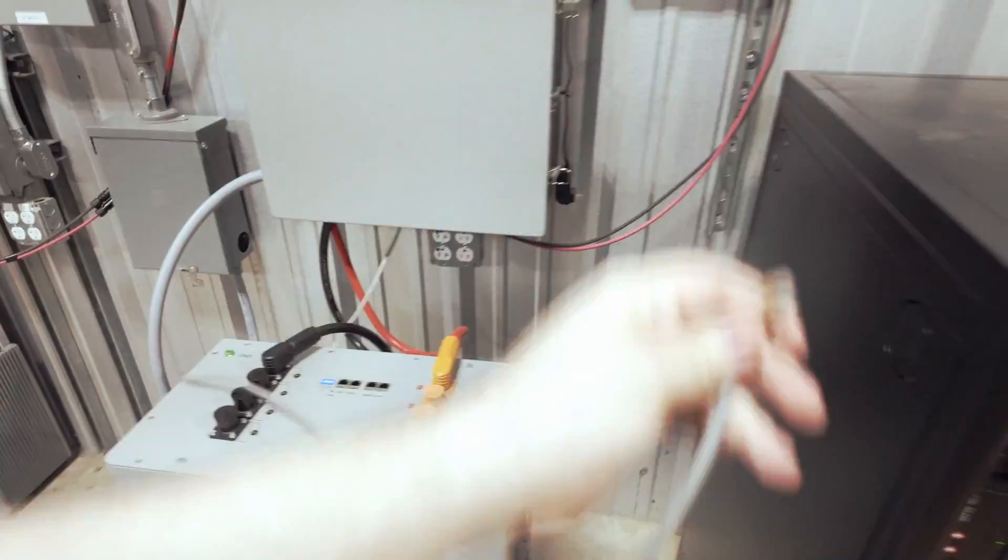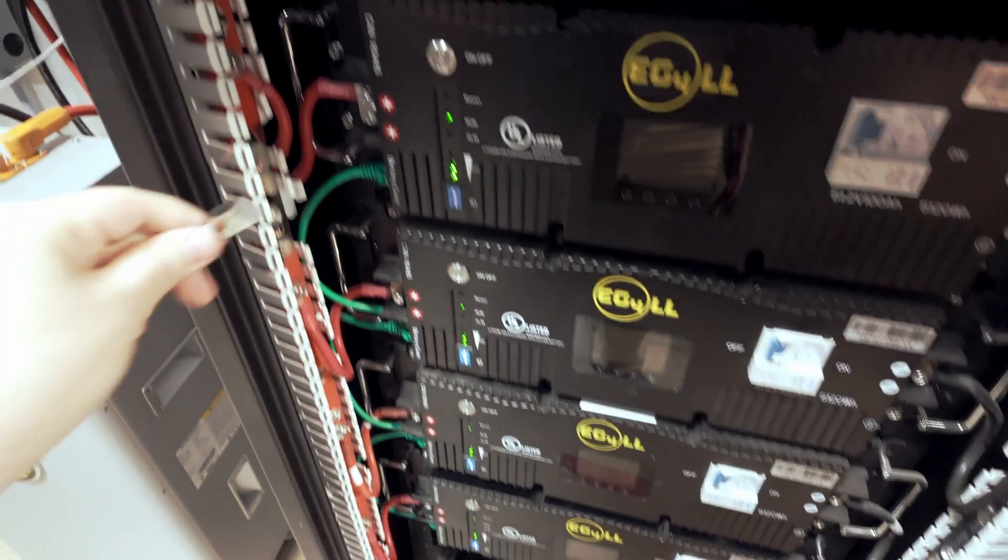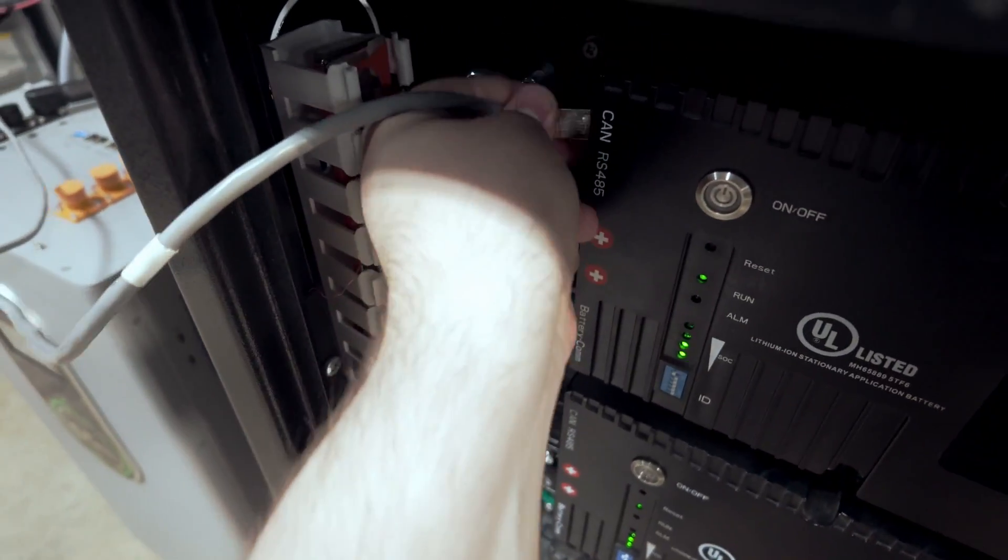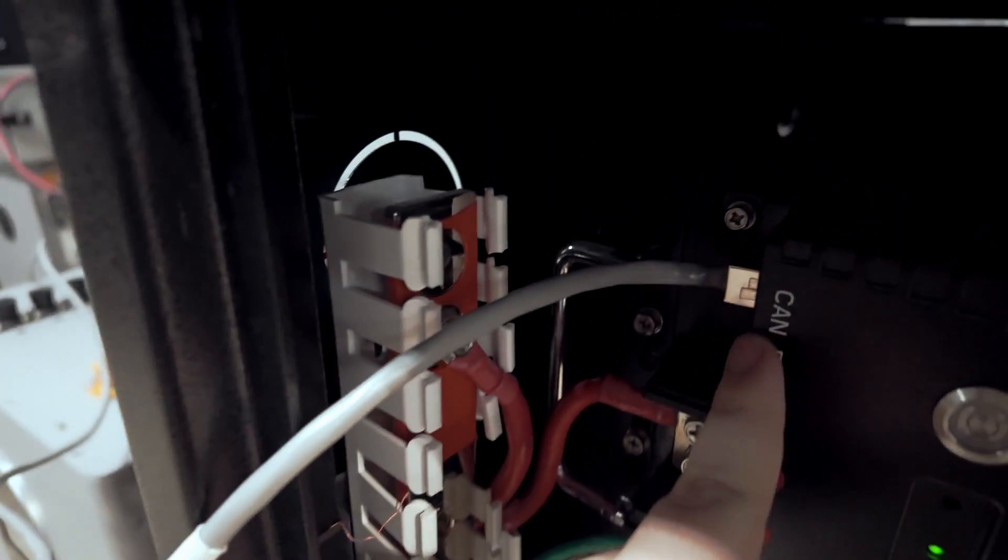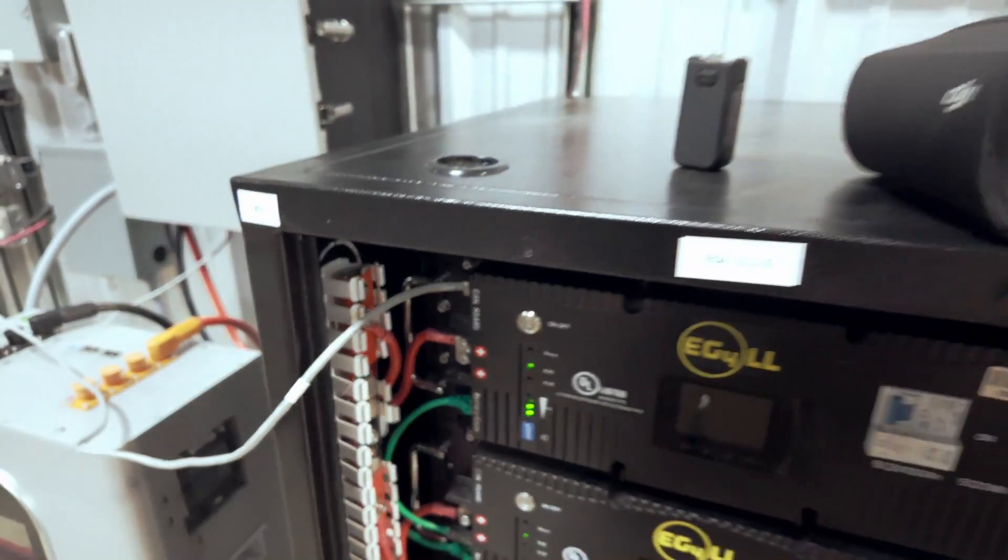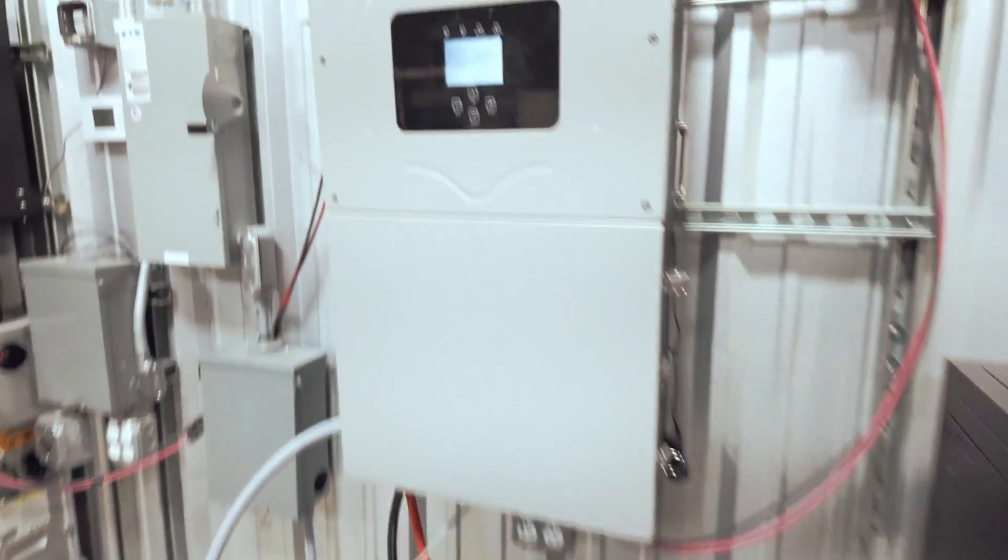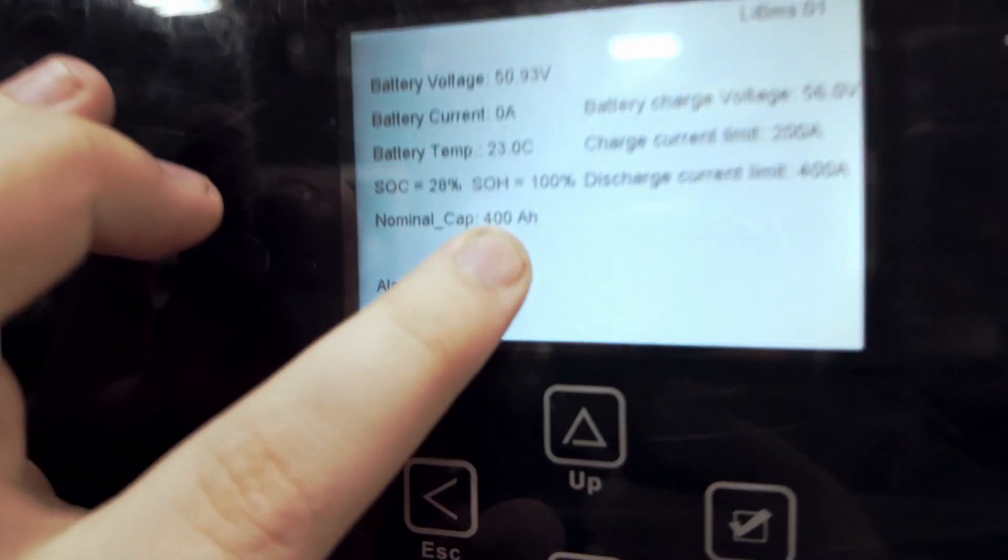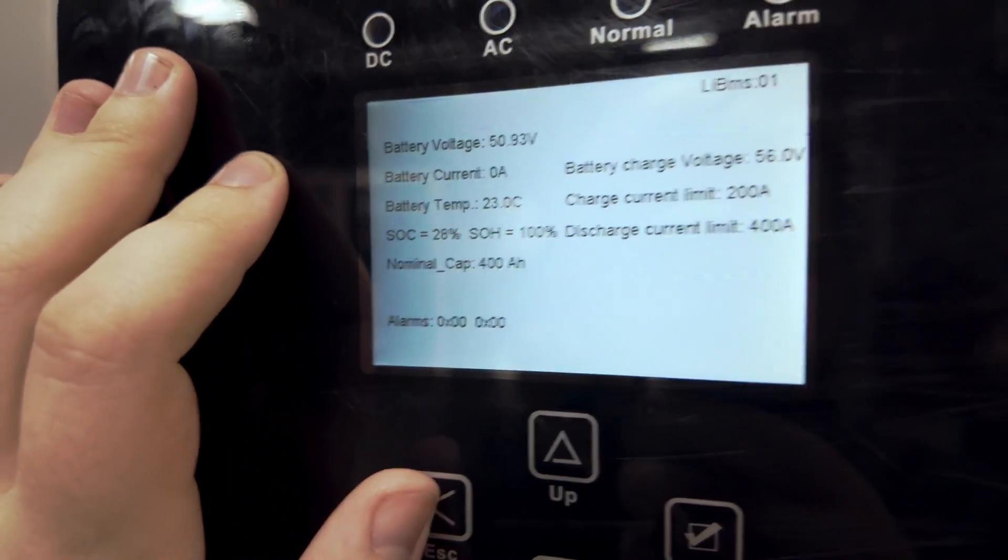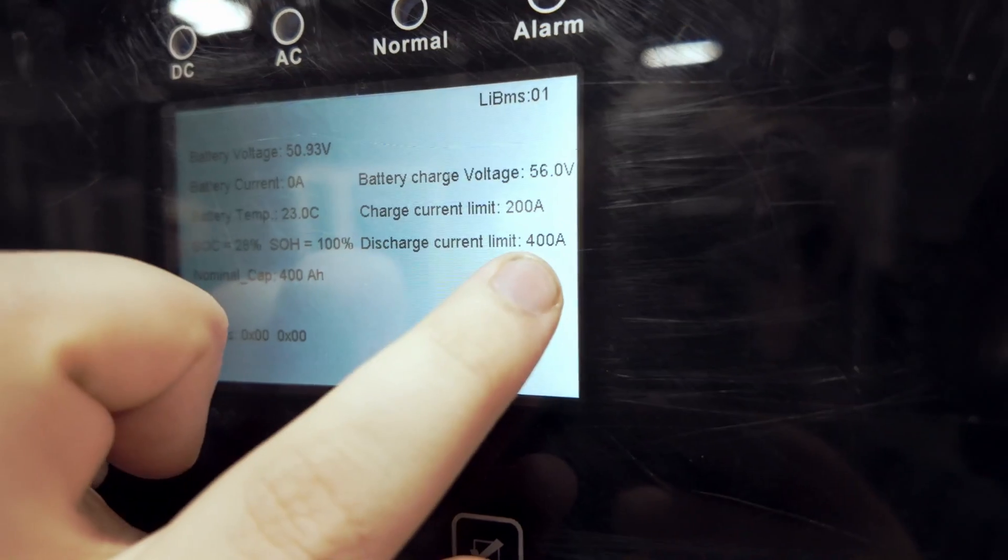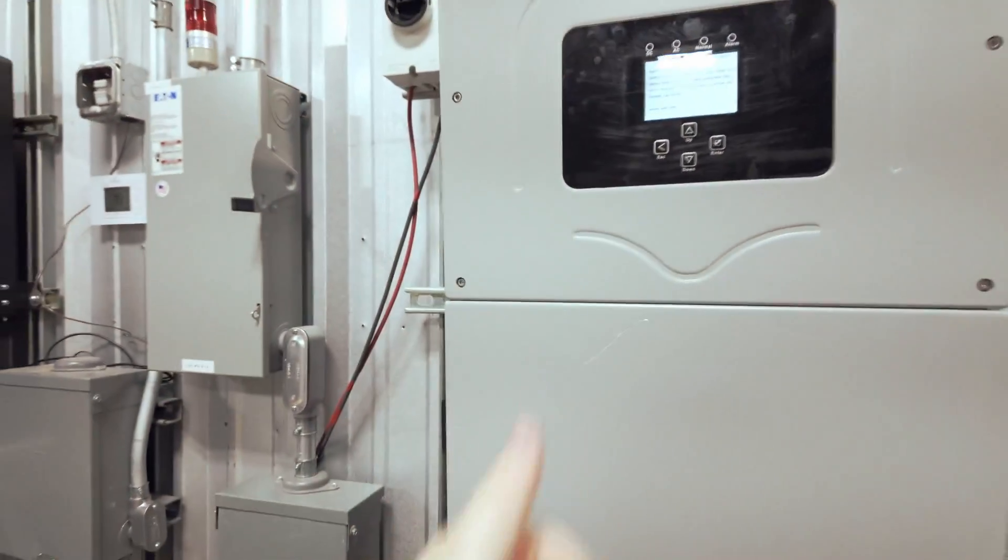Now this also goes for the LL batteries. So we have a stack of four EG4 LLs here. Again, you want to use the CAN port here, not the RS-485. I already have these set to the Solark protocol. And on here, we'll see that our nominal cap is raised to 400 amp-hours. Our charge current limit is 200. Discharge 400. Perfect.